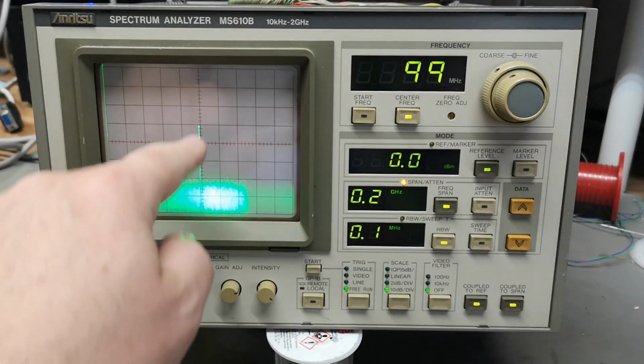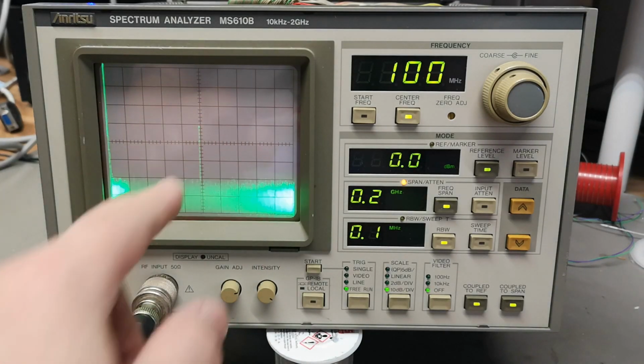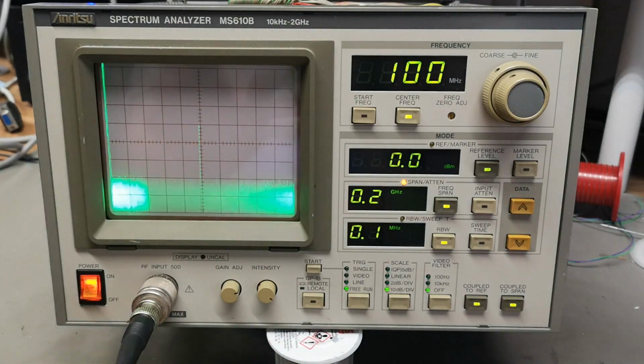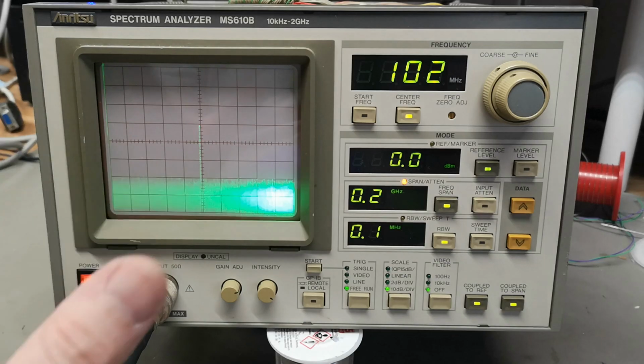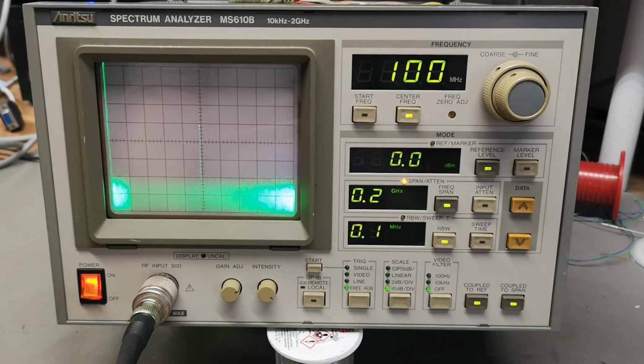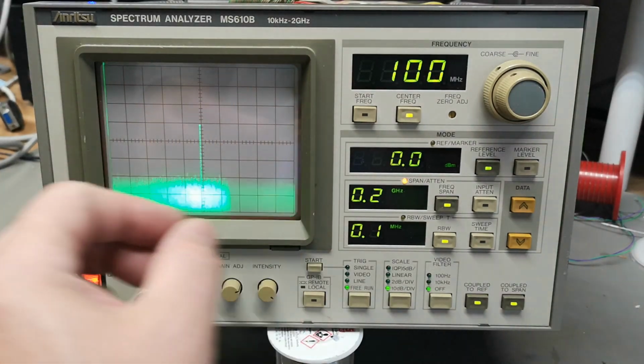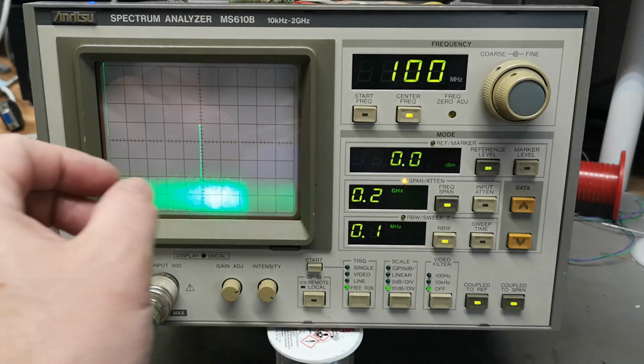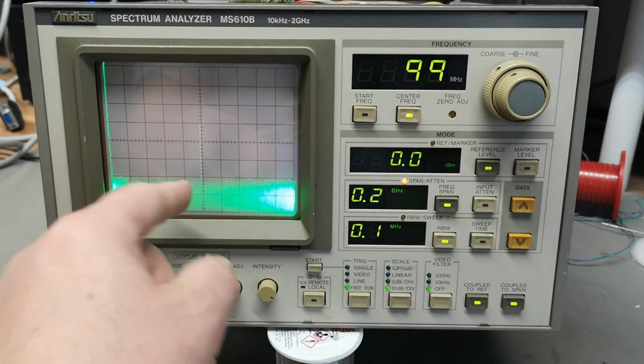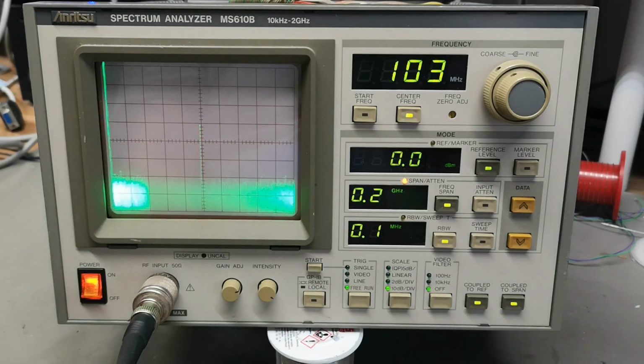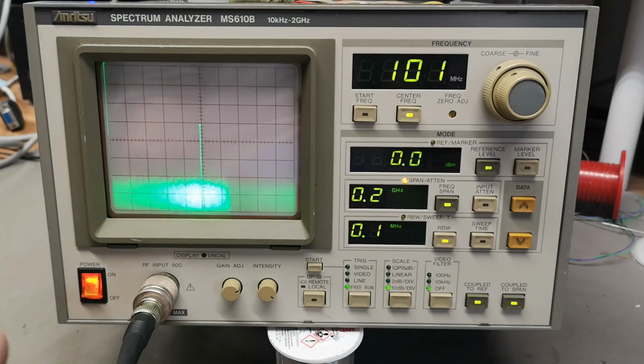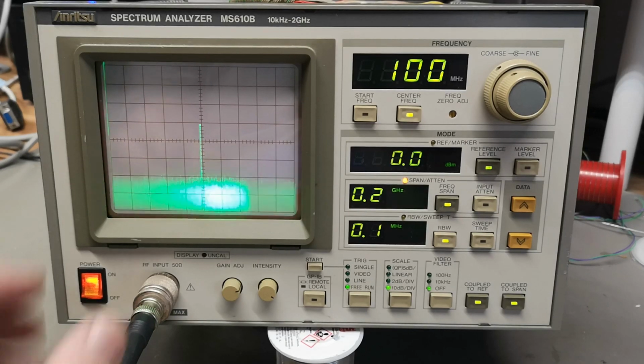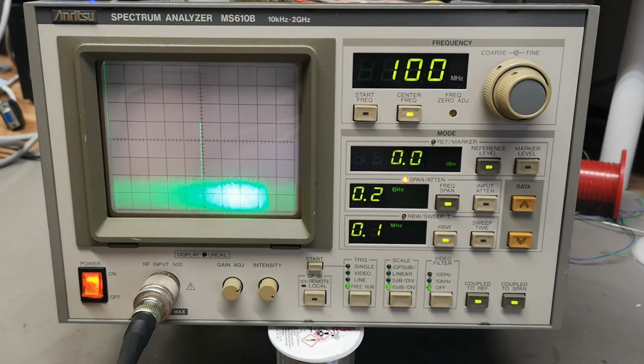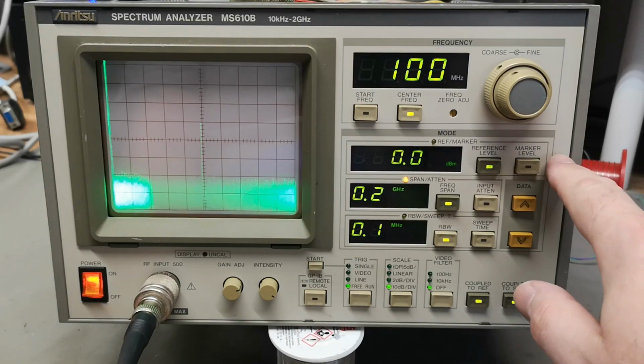So here's my 100. It's supposed to be exactly in the middle, and it is a little bit to the left, as you see. And here's what you do. Since everything here is of course analog, and it's just warming up, you need to wait a little bit until it's done warming up, and then everything will drift a little bit. The voltages that control the YIG will of course change a little bit, and then my 100 will of course be in the middle. So you need to wait a little bit before you do calibrations, and so I'll have to do that.